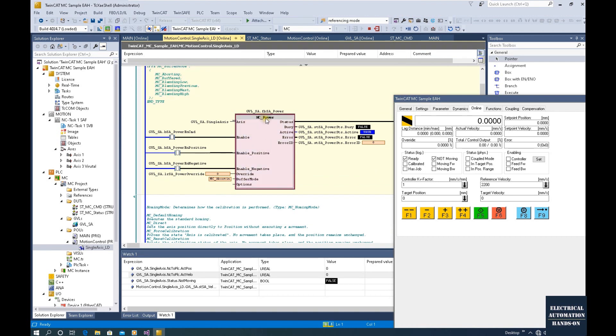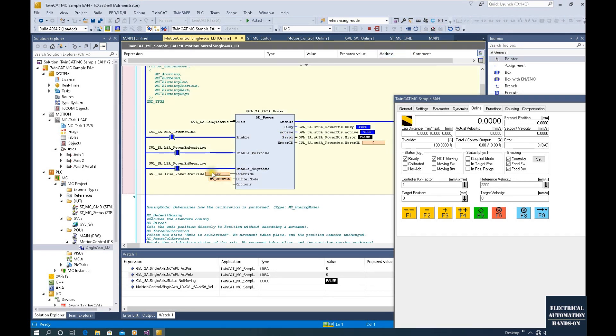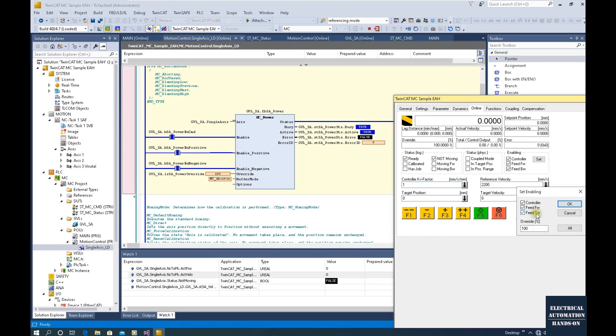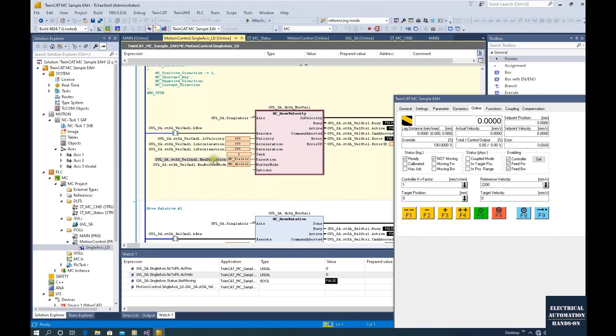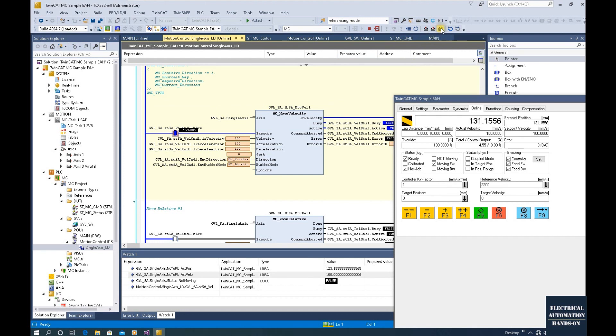Let's enable MC Power — enable both directions, positive and negative. We will see the enabling shows on, meaning the axis is enabled. After we enable this, don't forget the override — we need to set it to 100%. Now let's find MC Velocity here: I set the velocity to 100, and acceleration and deceleration to 200. These are the test values. Now if I trigger this Move Velocity and then shut down this execute, we will see the axis still keeps moving — it cannot be stopped.